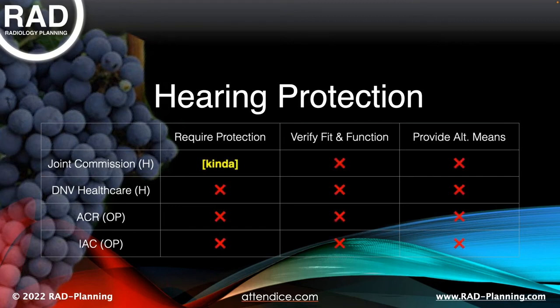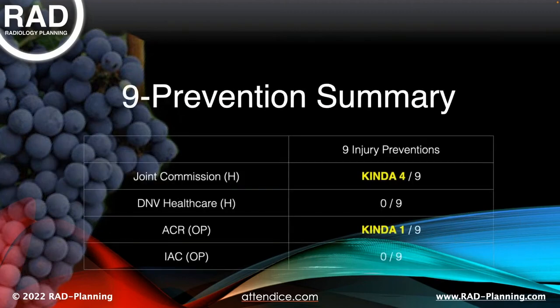Hearing protection, Joint Commission, again, doesn't require hearing protection. They require training for MR techs on the fact that hearing protection is important. ACR requires that there is some policy on hearing protection. Doesn't mean that that policy has to require hearing protection. Your ACR compliance policy on hearing protection could be hearing protection good, and that could be the end of it. So again, the overwhelming majority of accreditation criteria compliance looks awful in terms of preventing known mechanisms of patient injury in MR.